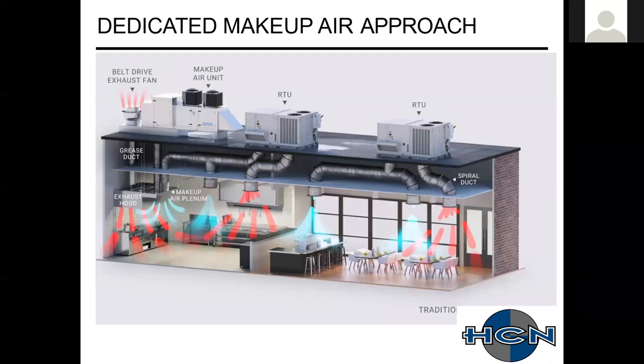And this is just a picture of the typical traditional system you've probably seen designed in the last five to 6 years. You're going to have your exhaust hood, your makeup air plenum, your dedicated makeup air unit, the dual plenum configuration with your rooftop unit. Hopefully these are perforated diffusers to create laminar flow, not a high discharge throwing some air into the space, and then the return air for the units as well.